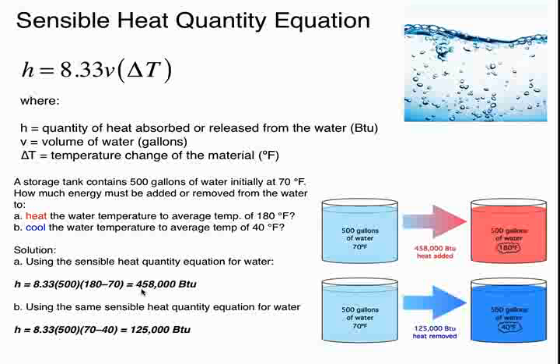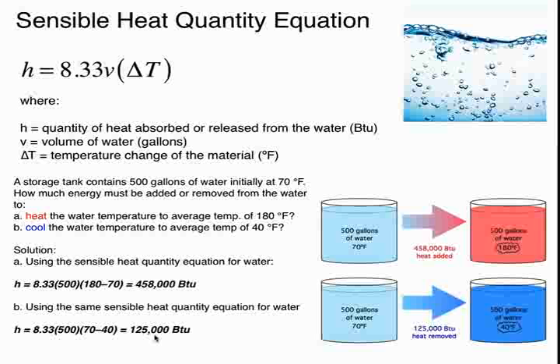Now, the same formula will work when we're taking heat out. Again, it would be the volume times the temperature change. So if we were to take 500 gallons of water at room temperature, 70 degrees, and run it through a chiller and bring it down to a uniform 40 degrees Fahrenheit, we would have extracted, according to our formula, 125,000 BTUs. So this formula is an easy formula to work with, and it works both adding heat and taking heat out of water.